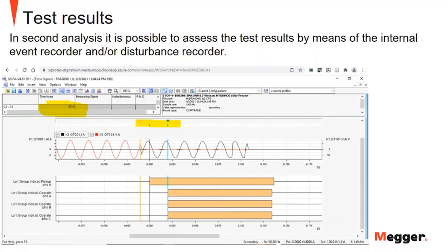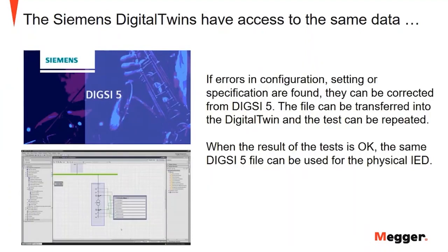And so very often tests are done this way. So if errors in the configuration, setting, or specification are found, then they can be corrected from DIGSI 5. The file can be transferred into the digital twin, and the test can be repeated. When the result of the test is okay, the same DIGSI 5 file can be used for the physical IED. I load the result into the physical device.